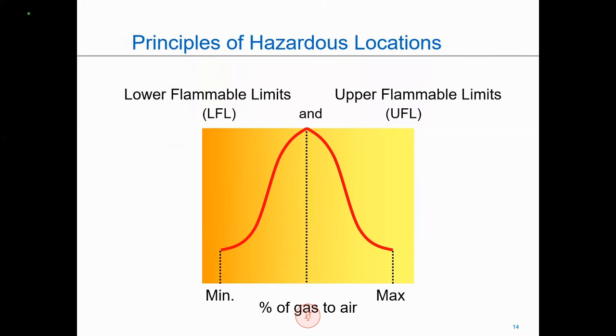Now, I mentioned we need to have proper proportion for there to be able to be an explosion. When it comes to gases and vapors, here I'm talking about my lower flammable and upper flammable limits. With this particular situation, anywhere in between the minimum and maximum is a volatile mixture. If the mixture of gas to air fell to the left of the minimum, it would be too lean to be able to have an explosion. If it fell to the right of the maximum, it'd be too rich to have an explosion. And anywhere in between, as I said, it's going to be a volatile mixture.